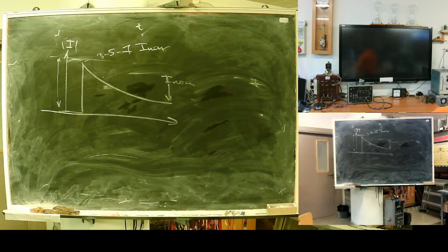Actually, this one has an instant current that can be selected starting from 1125. No, sorry. It's instant 1600. This one trips instantly at 1600 amps.